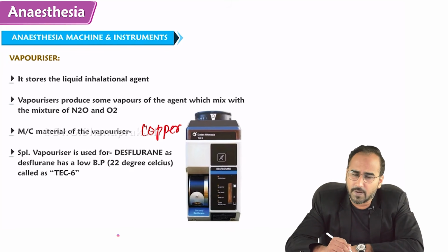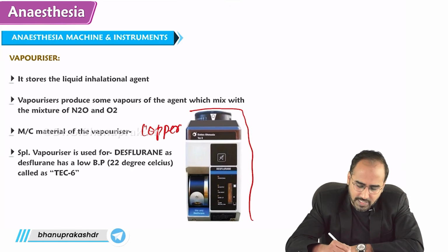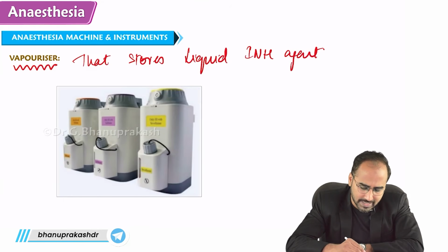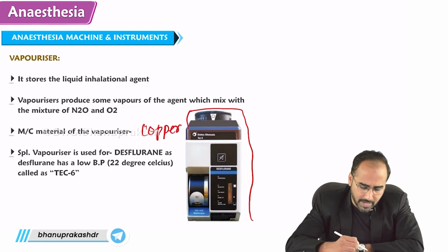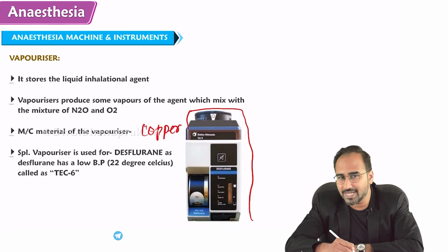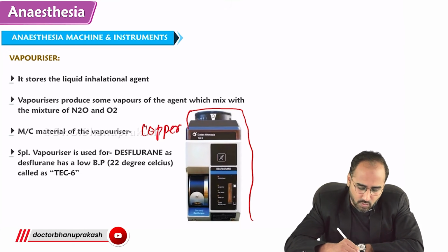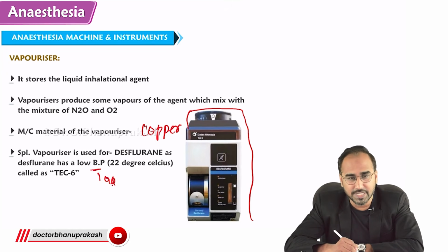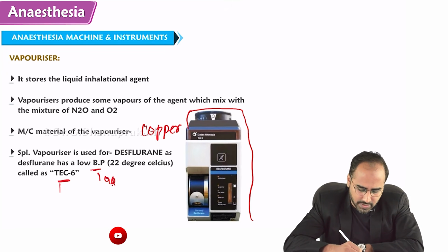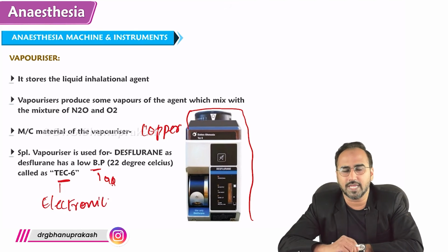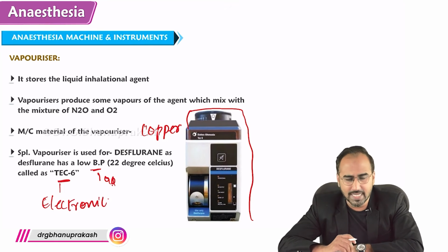So this device is made up of copper, but a special vaporizer is required. This is a special vaporizer. Normally all vaporizers look like this. Okay? But a special vaporizer is required for a special gas called desflurane, which is very costly. Remember guys, desflurane requires a special vaporizer. Why? Because it has a low boiling point. This vaporizer that is used for desflurane is also called Tec 6 or electronic vaporizer. That was regarding the vaporizer.